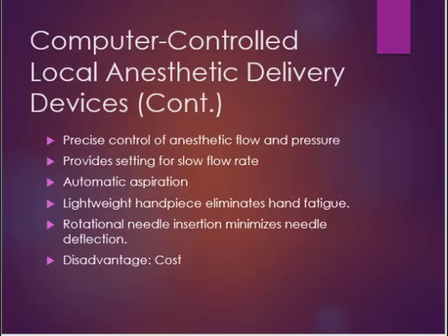Okay, with the computer-controlled local anesthetic delivery device, there's going to be precise control of the anesthetic flow and pressure. There's a setting on it that you can change for a slow flow rate. It does have an automatic aspiration. It's lightweight and it eliminates hand fatigue associated with injections.